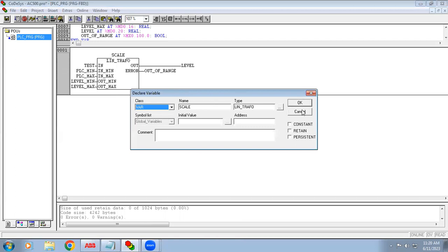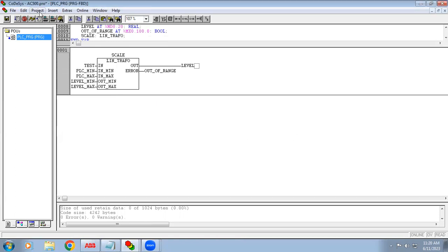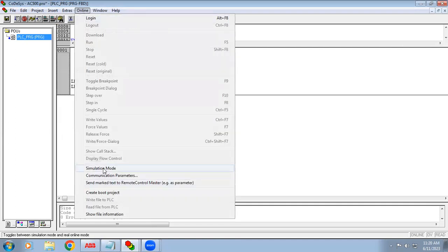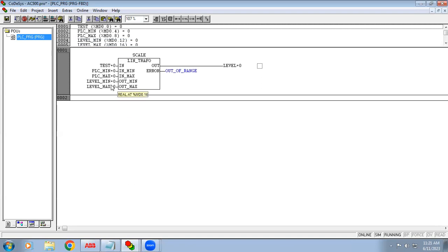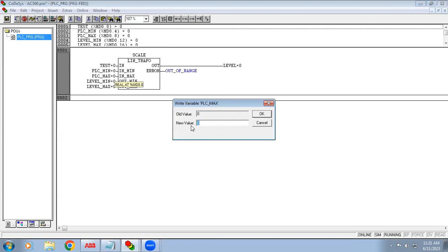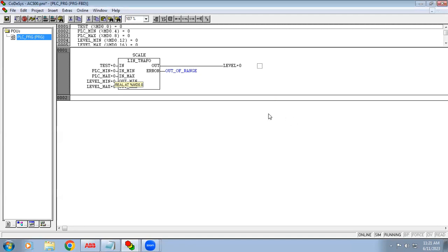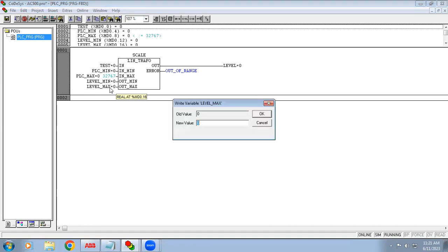Give build to compile, then enable simulation mode, login, and run. Right now minimum and maximum are both equal, that's why it's showing out of range. In the PLC it reads the value in terms of 0 to 32767, and I want to read this in terms of liters — 0 to 5000 liters.